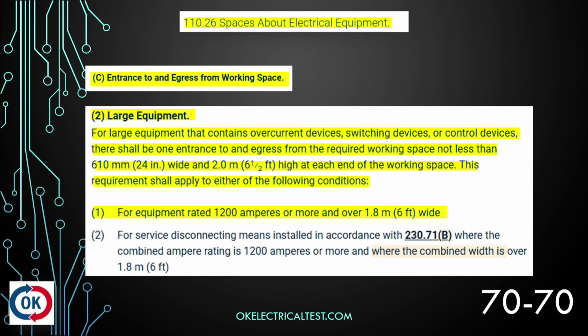Now, number 2, large equipment. It says for large equipment that contains overcurrent devices, switching devices, or control devices, there shall be one entrance to and egress from the required working space not less than 24 inches wide and 6.5 feet high at each end of the working space. So now they've clarified, hey, if I've got large equipment, not only do I need to have one on each side of the working space, but I also need them to be at least 24 inches wide and 6.5 feet high. And that's number 1 for equipment rated 1,200 amps or more and over 6 feet wide. So what's large equipment? That's equipment that's over 6 feet wide.